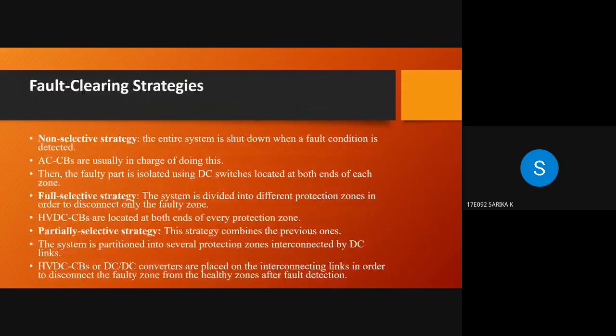Fault clearing strategies. This consists mainly of three types of strategies. They are non-selective strategy, full selective strategy, and partially selective strategy. First, non-selective strategy. The entire system is shut down when a fault condition is detected. AC circuit breakers are usually in charge of doing this. Then the faulty part is isolated using DC switches located at both ends of each zone.